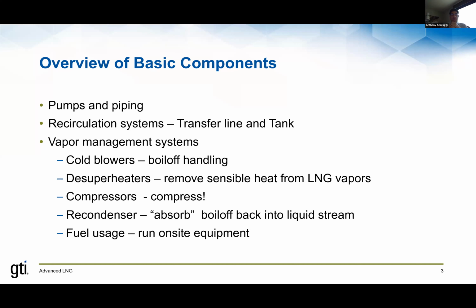the concept of boil off. That boil off has to be taken care of somehow. You can't leave it in your tanks, whether it's an on-land tank or whether it's a ship. You have to somehow handle that boil off. If you don't remove it from a closed system, you'll eventually pressurize the system, and LNG systems are not pressurized systems. So there are units that are called cold blowers that are generally used in LNG facilities, and all a cold blower is a compressor that removes the boil off, removes the vapor generated from the boiling LNG, pressurizes it a bit, and pushes it out of the tank into a piping system.